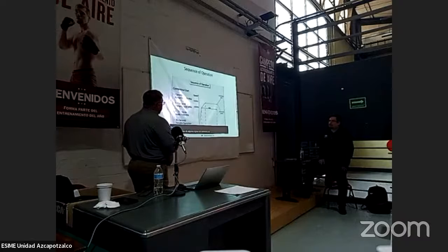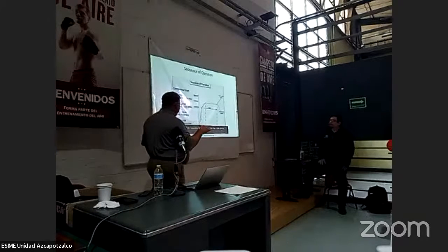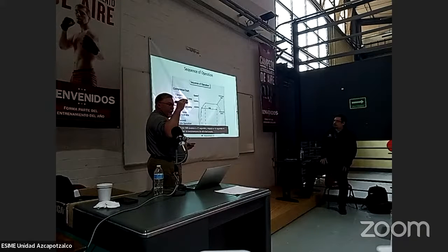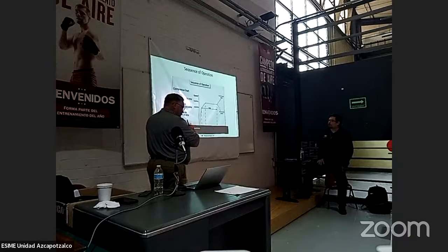So we'll talk about some sequence of operation. When the compressor starts up, in the first 2 seconds it's going to ramp up to 1200 RPMs. It'll stay at 1200 RPMs for 3 to 7 seconds, then it's going to ramp up to 1500 RPM. It's going to hold that 1500 for 8 to 17 seconds. After 18 seconds, that's when it will start its variable speed operation. So that's when it starts to modulate. It's got to take that time to figure out the position and also have all the communications going back to the VSOU, to the boards, to the thermostat. All of that will come together to determine what position the compressor is in.